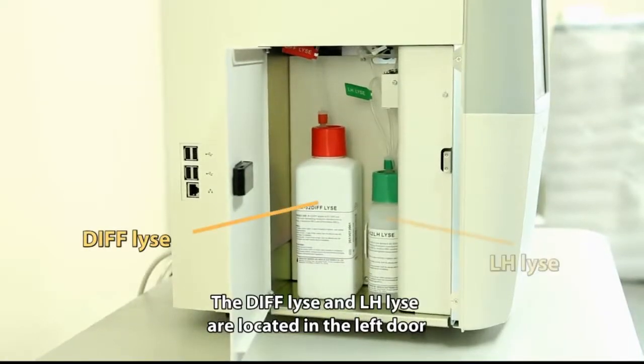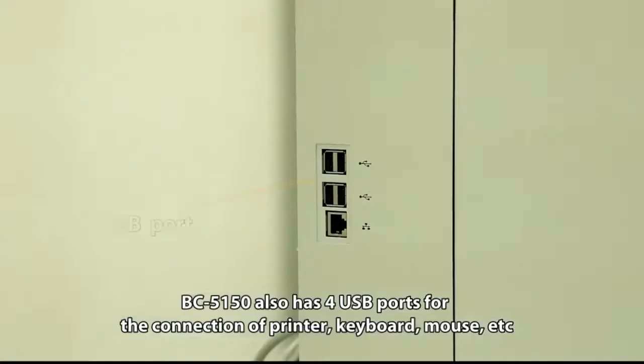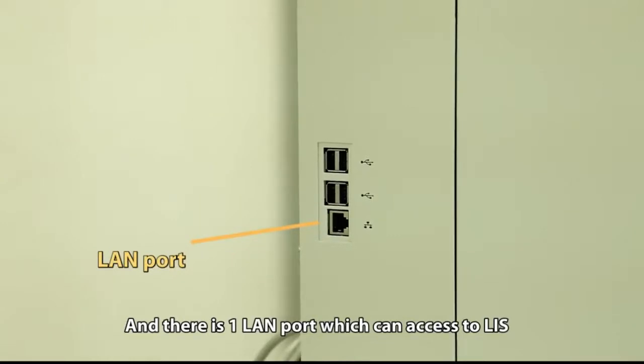The DIFF lyse and LH lyse are located on the left door. The BC5150 also has four USB ports for the connection of a printer, keyboard, mouse, etc. There is also one LAN port which can provide access to LIS.